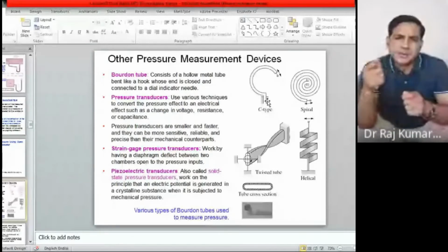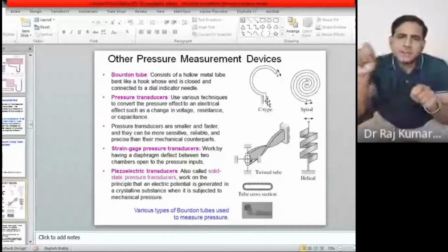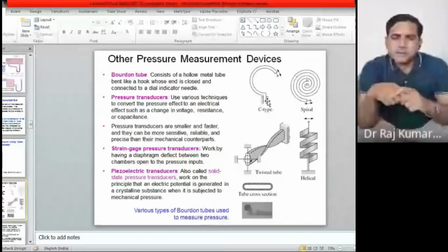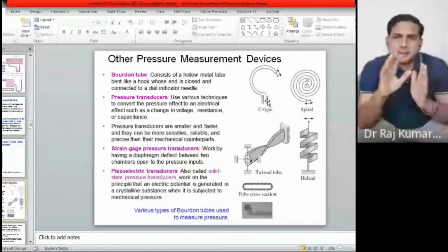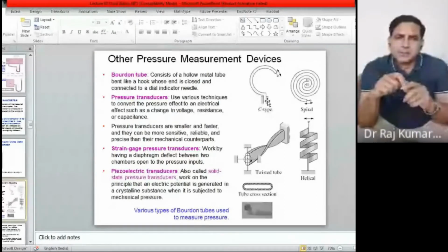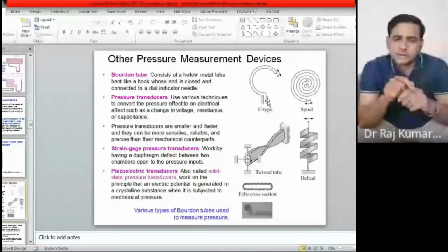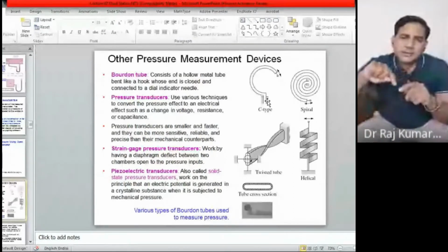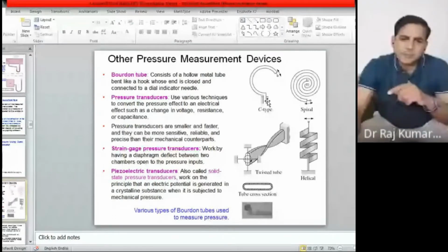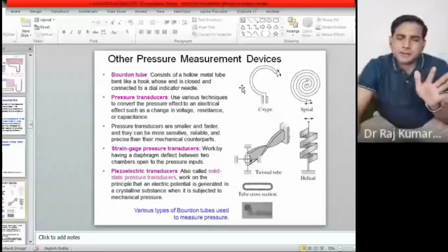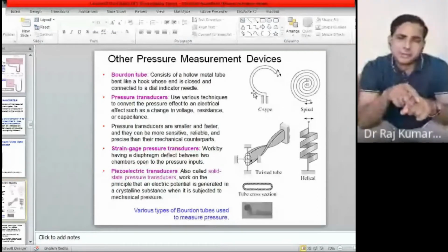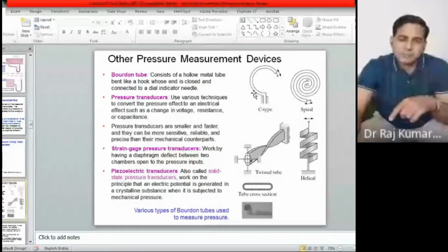When you pressurize that particular tube, it expands in length actually. And it is in a calibrated manner. It's not that for some pressure it will expand more and for some less. No, it's not that way. Moreover, it guides the circle also, just like the C shape; the C shape will not get distorted. It is not designed in such a way that it becomes completely flat. No, it will just move in that way. So if you put a pressure here, this pointer will move, and there would be a pointer connected at this particular point here.